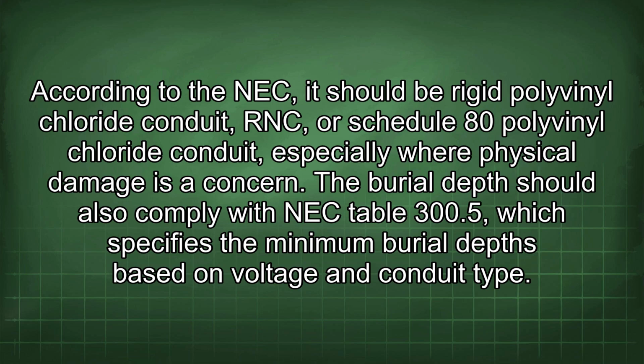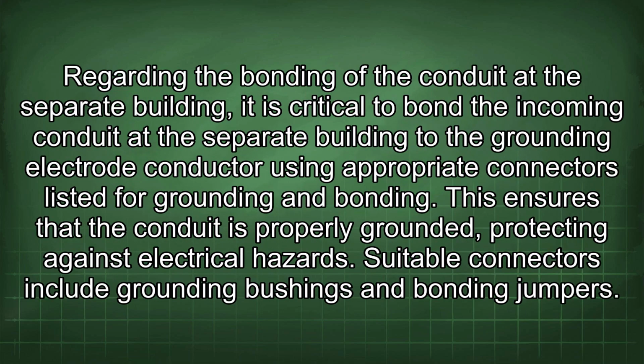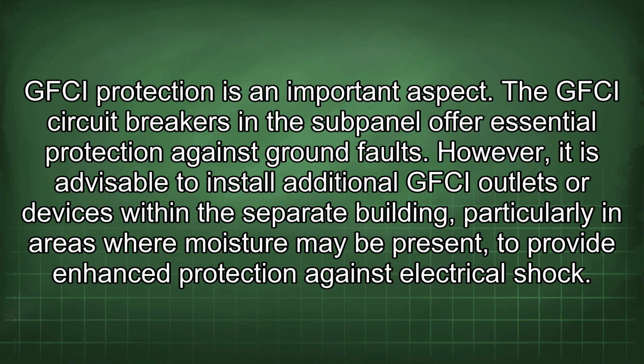The burial depth should also comply with NEC Table 300.5, which specifies the minimum burial depths based on voltage and conduit type. Regarding the bonding of the conduit at the separate building, it is critical to bond the incoming conduit at the separate building to the grounding electrode conductor using appropriate connectors listed for grounding and bonding. This ensures that the conduit is properly grounded, protecting against electrical hazards. Suitable connectors include grounding bushings and bonding jumpers.